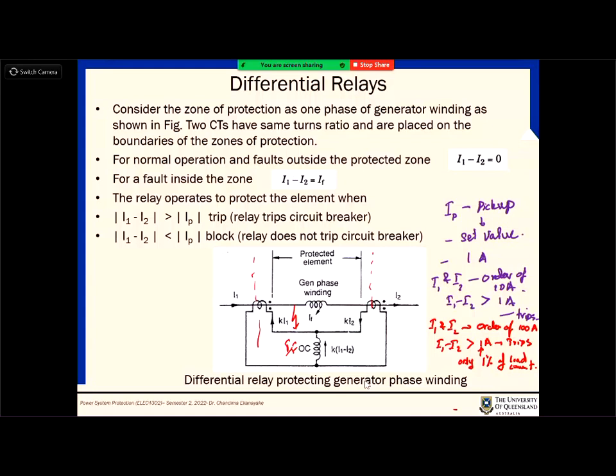This is the beauty of it. In the previous schemes, when you are considering the boundaries, you set something in the relay, because you are looking at the impedance. And the line conditions could change, so the protection zone could move further up or be shortened, because it depends on the line impedance, or line conditions. But in this case, it is fixed. As long as you have physically connected something in between, that is the protection zone. So that is one of the advantages of these differential schemes, that it's not affected by external factors like in the other two.